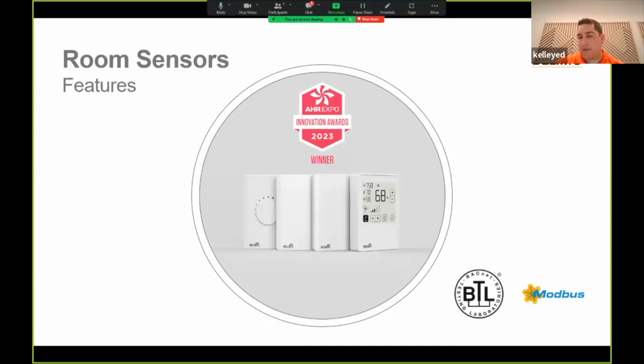All right, so before I kick over to Brett for the room sensors, one thing I wanted to point out: we got the AHR Expo Innovation Award last year on these new room sensors. In my eyes, there are three main reasons for this. Firstly, powerless NFC. These are all configured through NFC. Brett will give you the details of that. What's nice about the powerless NFC is you can have all of the room sensors in front of you in their original sealed packaging, and configure them before they get into your technician's hands. You can connect through NFC with one sensor, copy the settings and paste them to all the other sensors on the table in front of you. That way your technicians can go out and install these mechanically and electronically, and not have to worry about the setup and the apps and so on.